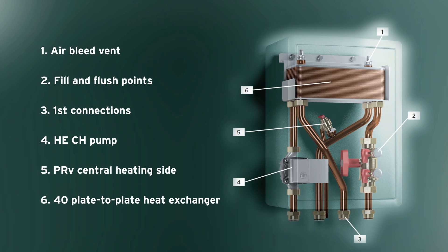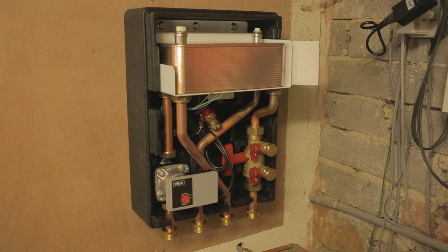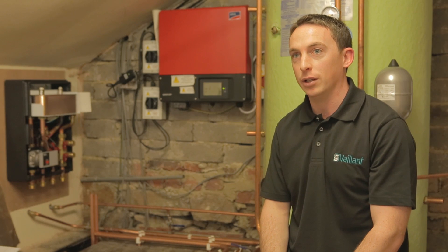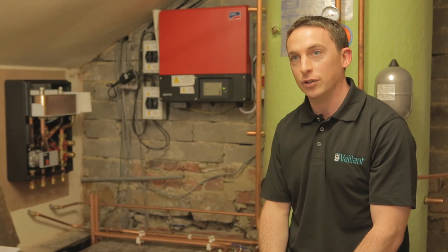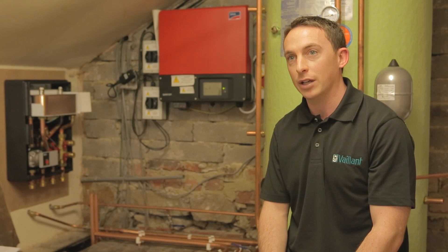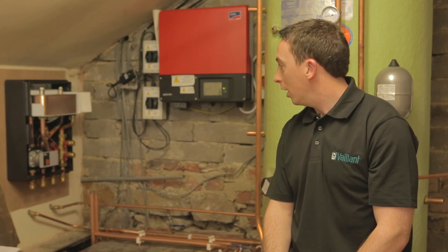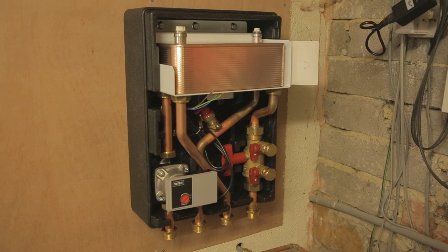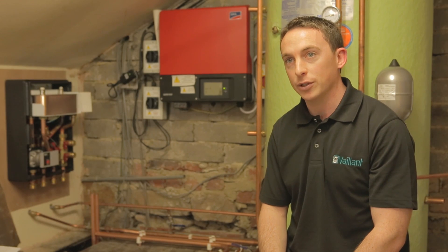The heat exchange unit supplied by Vaillant is a very unique product and it serves three purposes. Purpose number one is to separate the anti-freeze glycol fluid from the heat pump to the heating system. Second, it has a high-efficiency circulating pump which is 35% more efficient than a standard pump, and that distributes the heat around the heating system. Third, it has the fill and flush points to fill the glycol fluid from the heat pump outside the property to the heat exchange unit within the property.